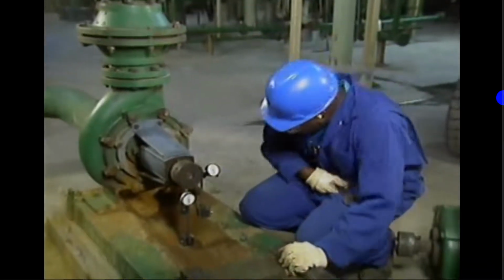A shaft alignment procedure can be futile if there are problems with the equipment being aligned. For example, shaft and bearing problems can prevent a component from being properly aligned with another component. One way to determine if these types of problems exist is to take runout readings on the stationary component and the movable component.